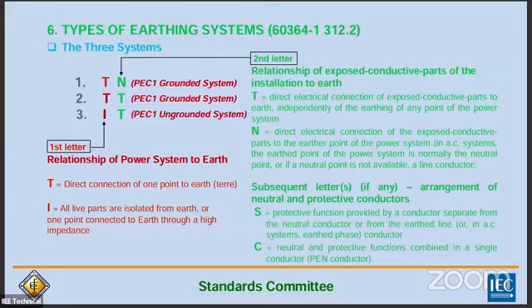So, ang tawag doon, yung pag may T ka doon, then TT, yan, grounded system pa rin yan sa PEC1. Yung TN, grounded system pa rin, so, dalawa lang. Pero dito sa IT, it's the ungrounded system. Then meron N, direct electrical connection of the exposed conductive parts to the earth point of the power system in AC systems. Okay, then subsequent letter, so TN, so meron kang C, ganon, TNC. Okay, then neutral and protection functions combined in single conductor, yung PEN, yung combine yung protective earth mo sa neutral.